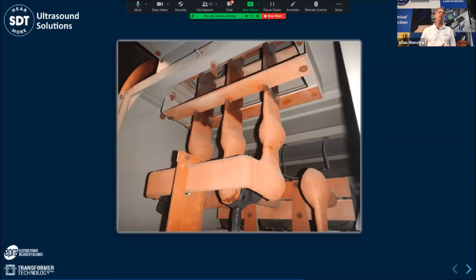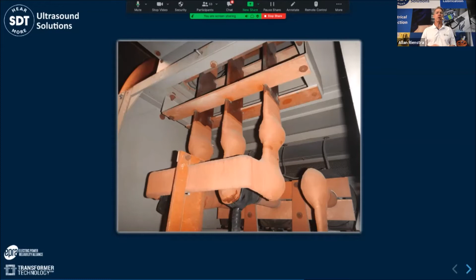What that tells us is that the symptoms of partial discharge are sometimes intermittent - sometimes you can see them with an infrared or ultraviolet camera, and sometimes you can hear them with an ultrasound camera. So going back to those condition monitoring technologies, ultrasound might be first, but that doesn't mean it's the best. They're all complementary, and in this particular case, ultrasound revealed the problem the earliest.